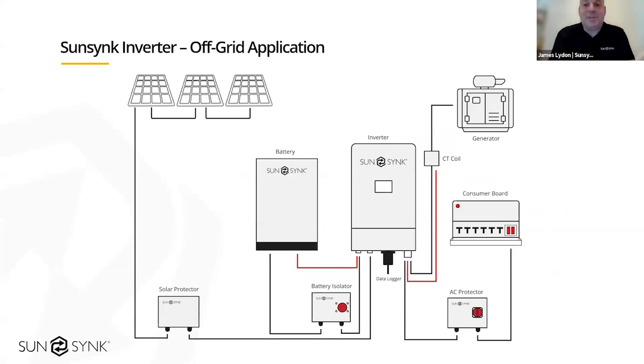Off-grid. As I mentioned earlier, all of our inverters will work completely off-grid. We don't need that grid supply. And this is just showing with the backup generator connected. With the backup generator connected on a completely off-grid site, the installer can program the inverter to say, if the batteries get down to 30% SOC, there's a contactor within the inverter that will close, that will send the signal to the generator to turn on. And then, as I mentioned, when that generator turns on, the power comes into the inverter and it will split two ways to both power the load and charge the batteries.